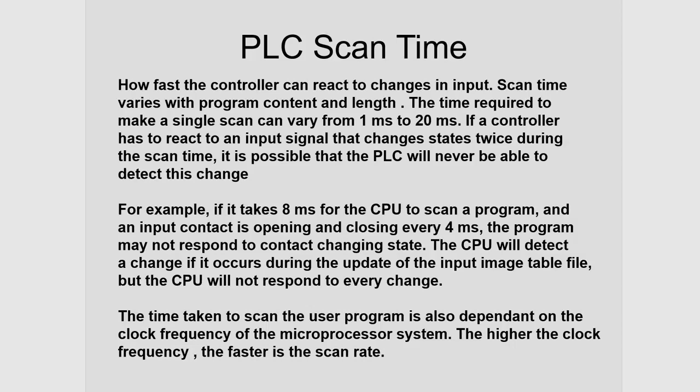So it's understood then that it takes time to go through the whole scan operating cycle. It takes time to look at the status of a switch, to update the input image table, and then to look at your logic, and then for that logic to react by making the rung true or false, and then to update the output image table, and then to turn on or off some device.